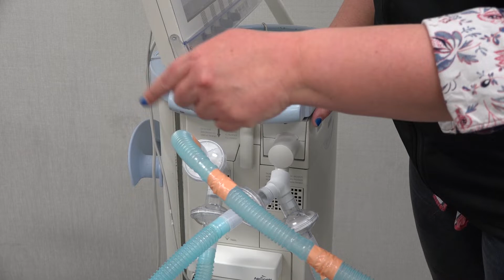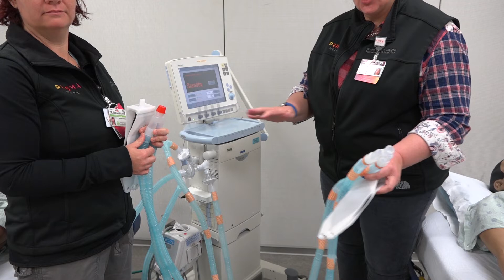You want to make sure that one patient in the dyad has the cap still attached to the circuit, and you want to make sure that you keep that cap, because it's going to be very important not only to test the system before you place the patient on it, but also that in case of an emergency, that cap is available, and when you want to take one patient off. So the first thing that you want to do after you set up the ventilator is test your system, because you want to make sure that you don't have leaks on both patient A and patient B.